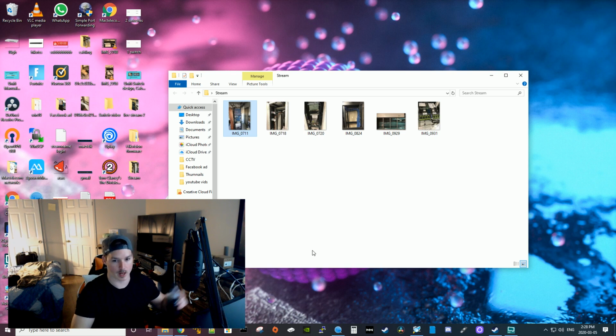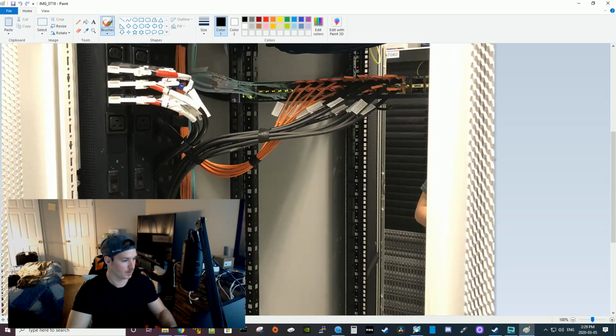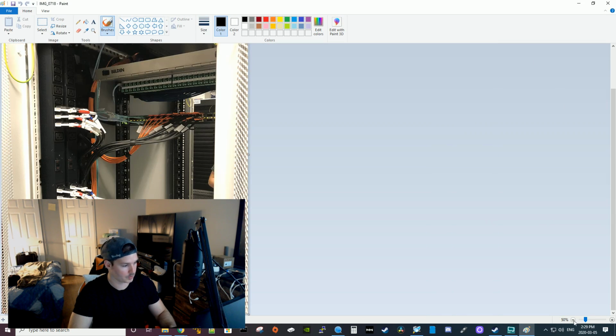Here's a few other racks. So this here is actually for Cisco UCS servers. And this particular cabinet has 2 different power sources, and they're on backup generators as well. So you could tell, let's put this in red, the red tape right here is on the red power supply, and then the blue is on the blue. So if you lost all power to this whole unit, the PDU, the blue side would still be up.